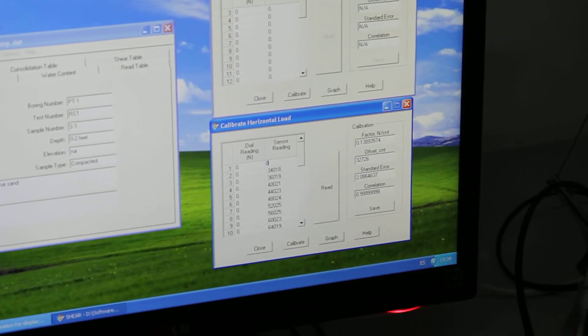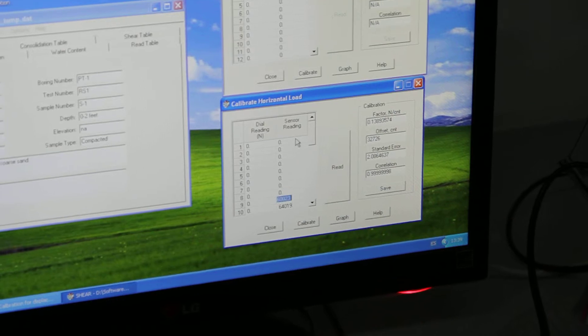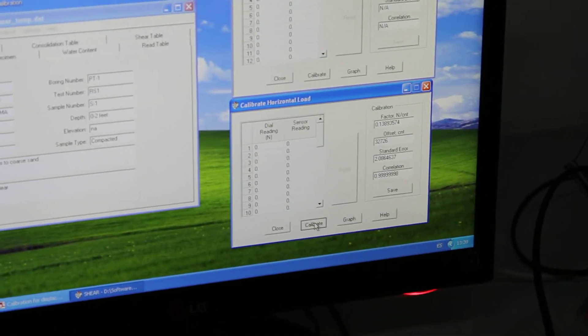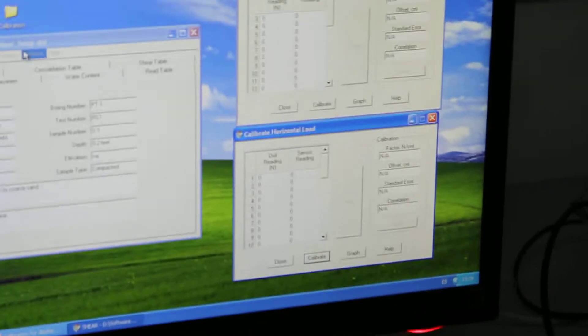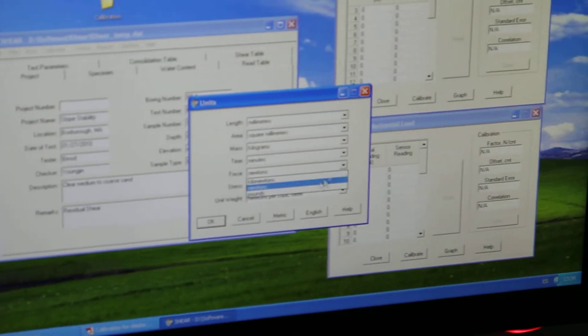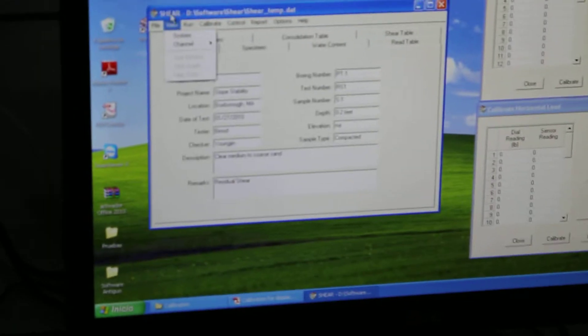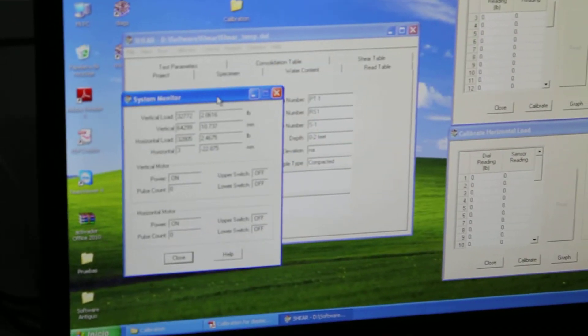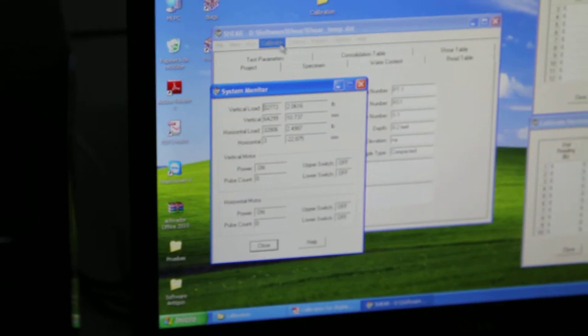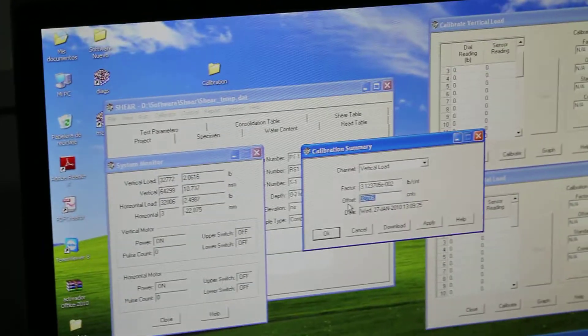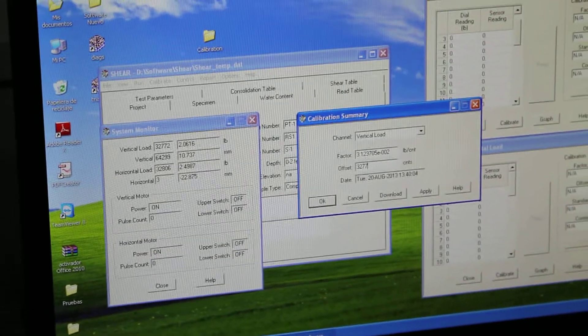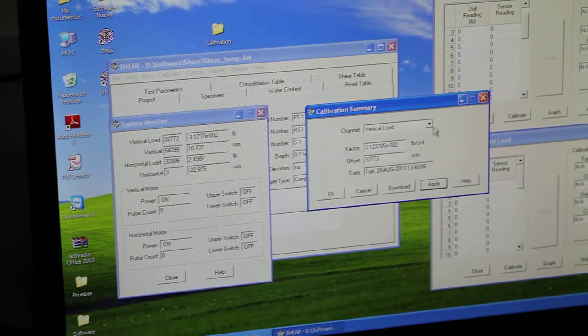And because my reference calibration cell is in pounds, I am going to change my force in pounds where you can use anything you want. And then I'm going to check my system. So this is right now showing the readings. But I am going to check my vertical and horizontal against the old calibration. So I'm going to zero my vertical and horizontal.